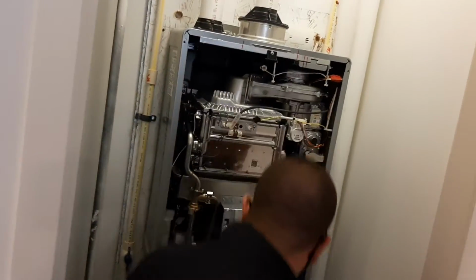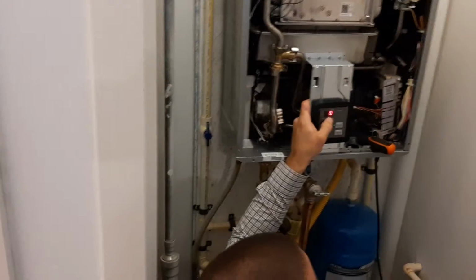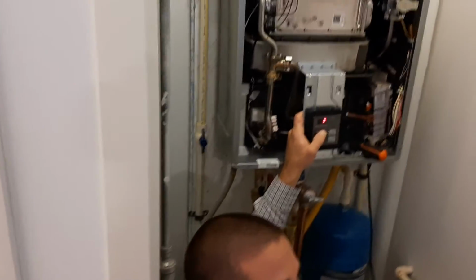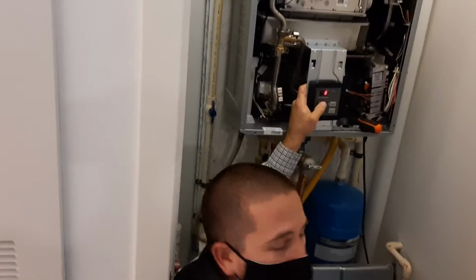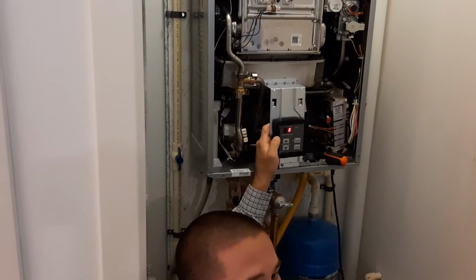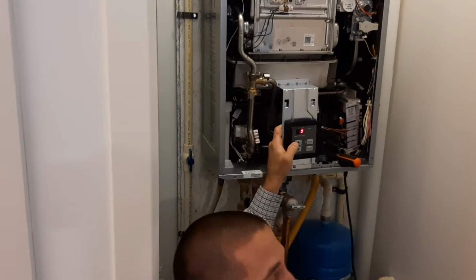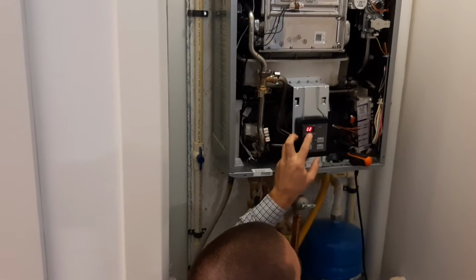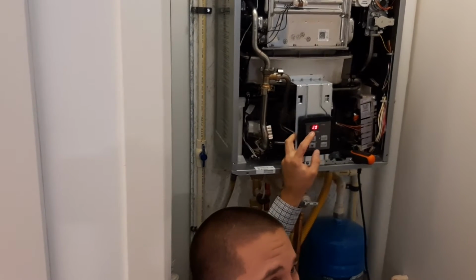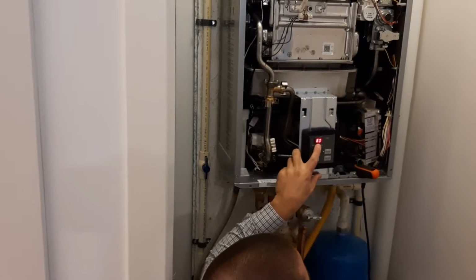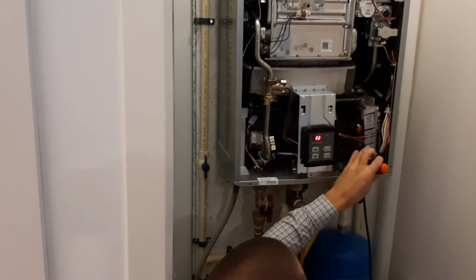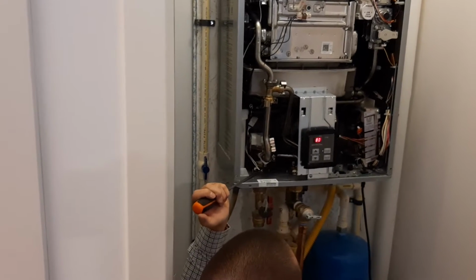So I got into that menu, and right now we're on status code 1 and it's saying 0. Status code 1 shows water flow, measured in tenths of a gallon per minute. If I go up to number two, that should show outgoing temperature. This unit's outgoing temperature is 80 degrees, measured right at that thermistor.